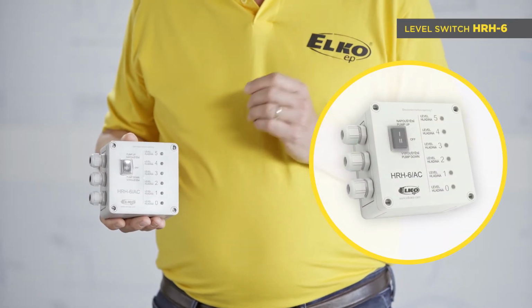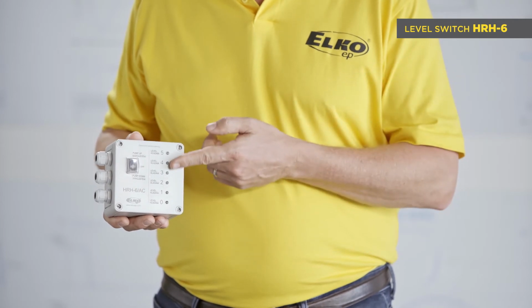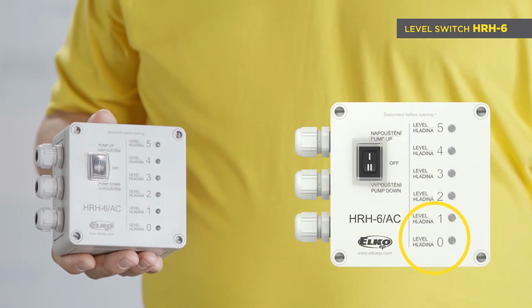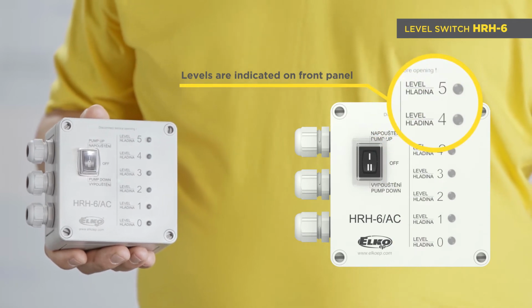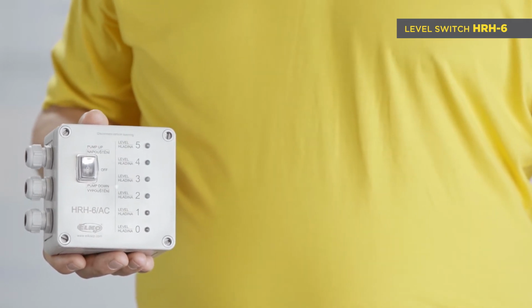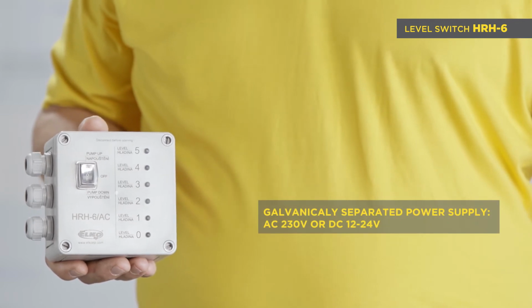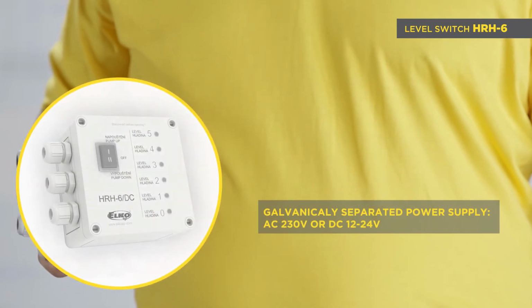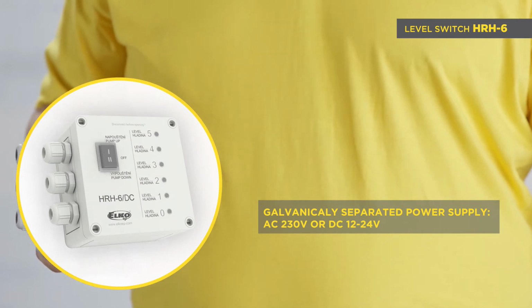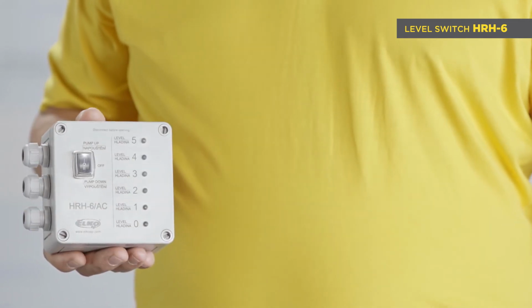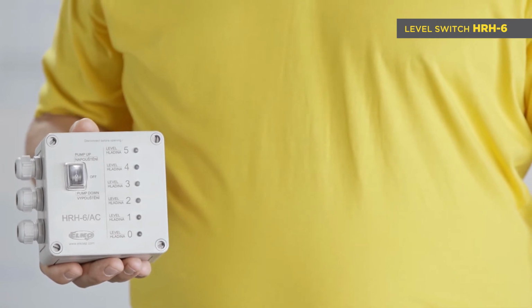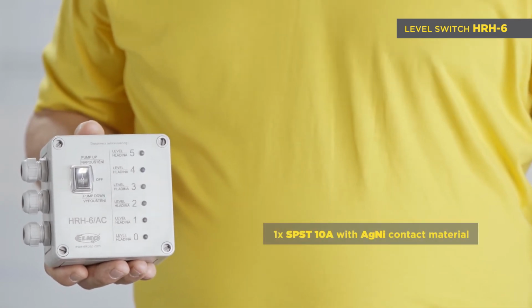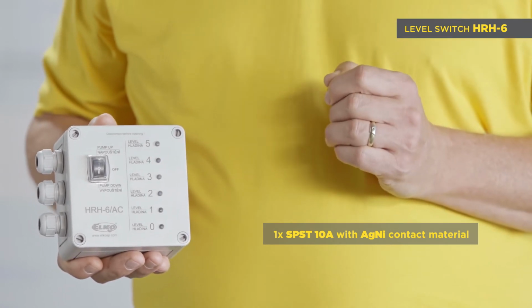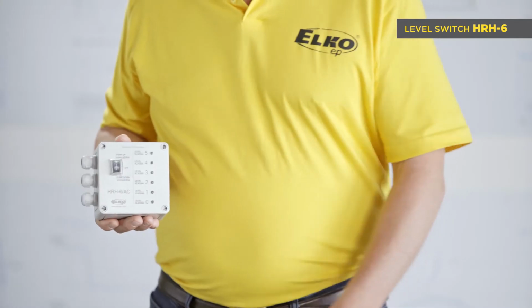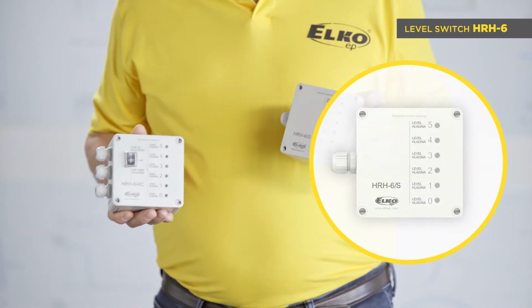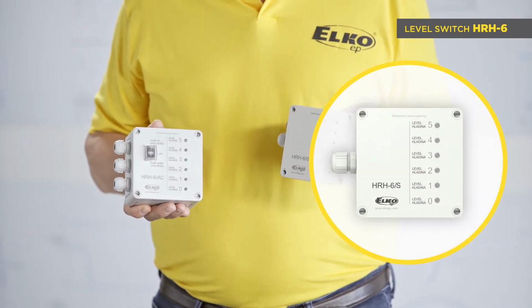HRH6 monitors 5 levels by using 6 probes, 5 for liquid levels, and 1 is common for all. Levels are indicated on the front panel of the device. There are 2 power supply options: AC 230 volt, HRH6 AC, and DC 12 to 24 volt, HRH6 DC. The DC option is intended for monitoring levels in truck tanks. One relay with SPST 10 amp contact is for signaling a full or empty tank. Also available is the auxiliary signalization panel HRH6S.